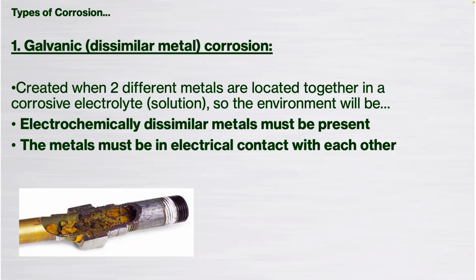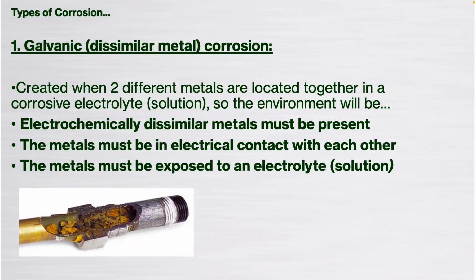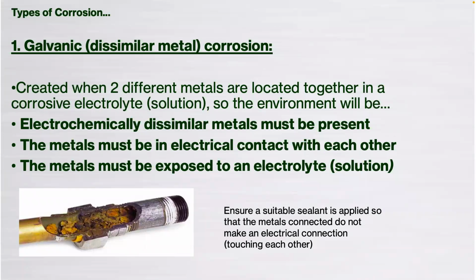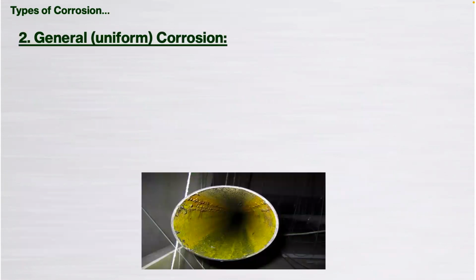So let's, for example, say in the picture that we're seeing here, a coupling was used. However, if we've got dirt and debris or corrosion deposit that starts to settle out, it almost acts as an electrical contact over the two pieces, and then we can start seeing localized galvanic corrosion. So it's only going to happen in the pipework. You can have flanges connecting pipework and bolts going through it. That doesn't give you the same concern because there's not an electrolyte within that. It's within the pipework itself. So that's, as I say, galvanic corrosion.